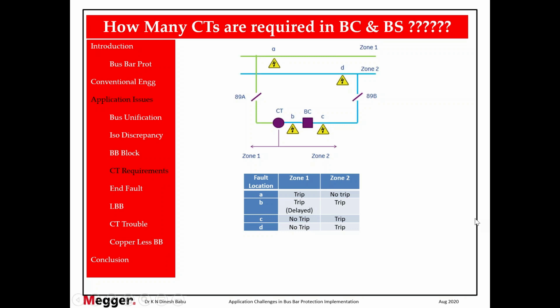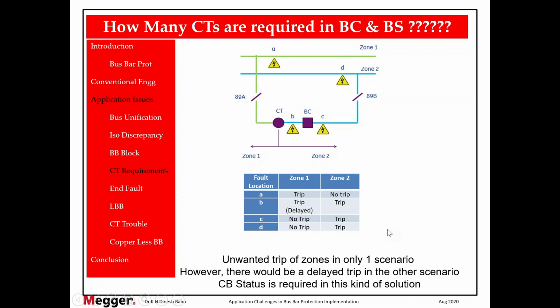So second question: what happens if the fault occurs at C? Only zone 2 trips, zone 1 does not trip. What happens if the fault is at D? Only zone 2 trips, zone 1 does not trip. So perfect. From this, what do we conclude? Unwanted trip of zones is only one scenario, whereas when you are using the 2 CT method, we have tripped in both the scenarios. But at the same time, we should understand that when the fault occurs in this region B, there would be a delayed trip.